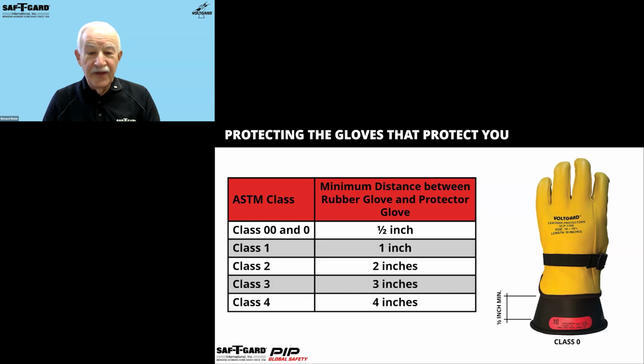The applicable ASTM specifications refer to the minimum distance between the edge of the protector glove and the cuff edge of the rubber insulating glove. It's a ½ inch for low voltage gloves and 1 inch per glove class for high voltage gloves. So knowing this, for example, the protector glove for a class 2 rubber insulating glove must be at least 2 inches shorter than the rubber glove. As illustrated on the screen, this is a low voltage class 0 glove, so the minimum distance is a ½ inch. This is the protection.